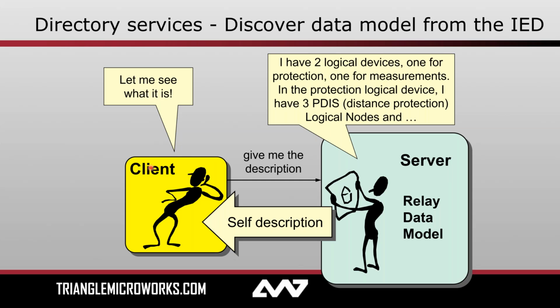Additionally, in a tool like TestSuite Pro, you're able to use this to compare the configuration that's actually loaded onto the server, discovered via the directory services, against an SCL file that you provide to your client. Basically, making sure that the configuration you're expecting, defined in the SCL file provided to the client, is what actually matches on the server. To give it a sanity check, if we look at this picture here, we see a picture of a house. This guy knows what house he wanted to build. Let's go ask the guy what house he actually built and make sure that the two align.